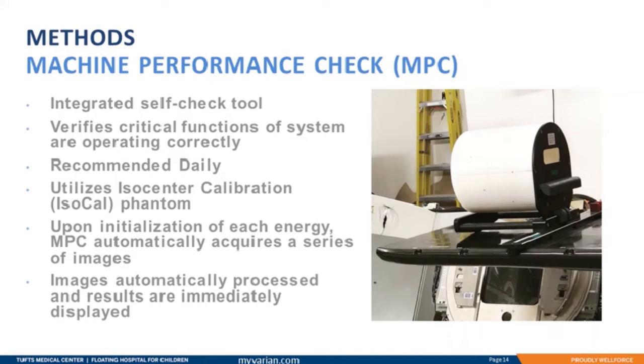The application is designed for reliable and fast system testing on a daily basis before routine treatment starts. Performing Machine Performance Check beam and geometry checks requires the IsoCal Phantom, seen here, to be mounted to the couch. After imager calibration, baselines are captured with IsoCal Phantom at a specific couch reference.